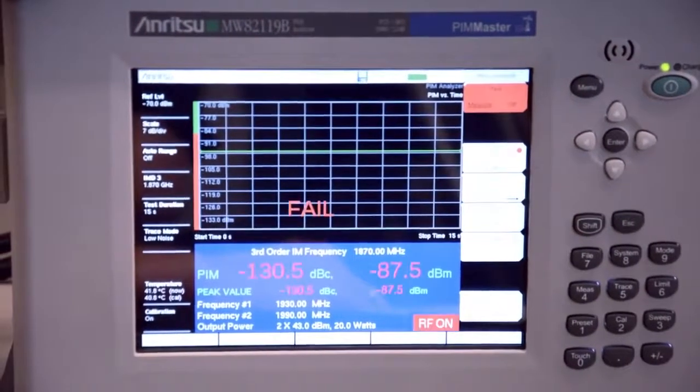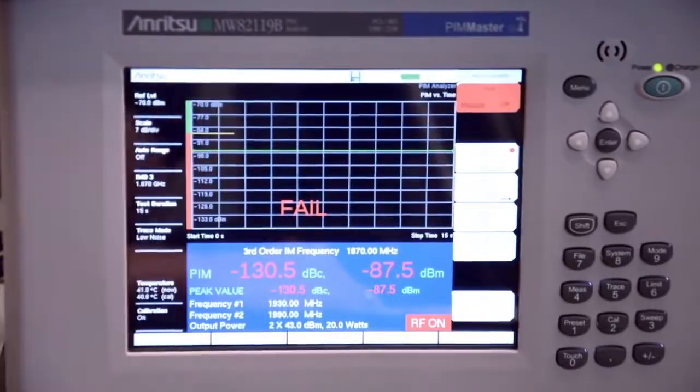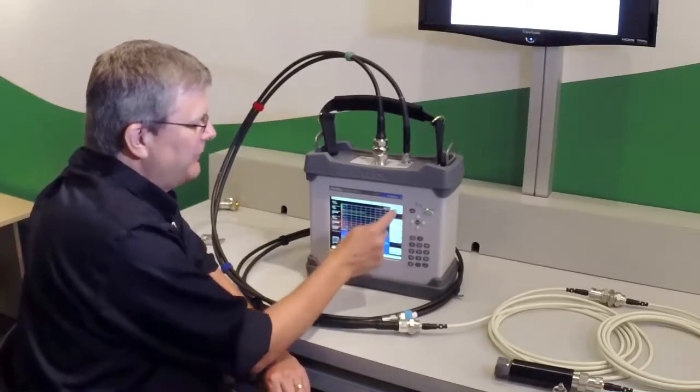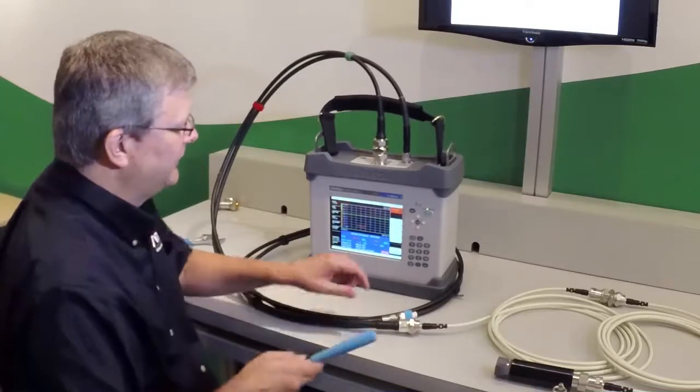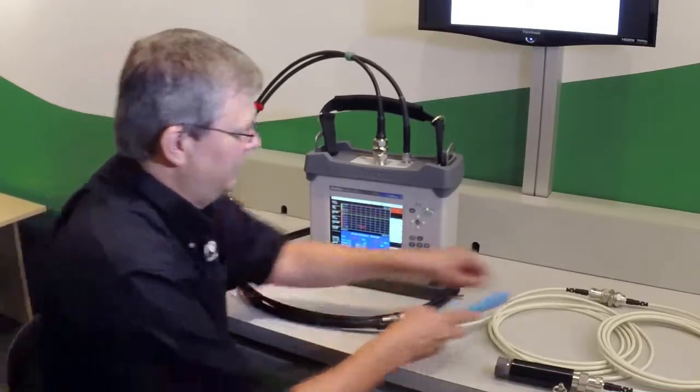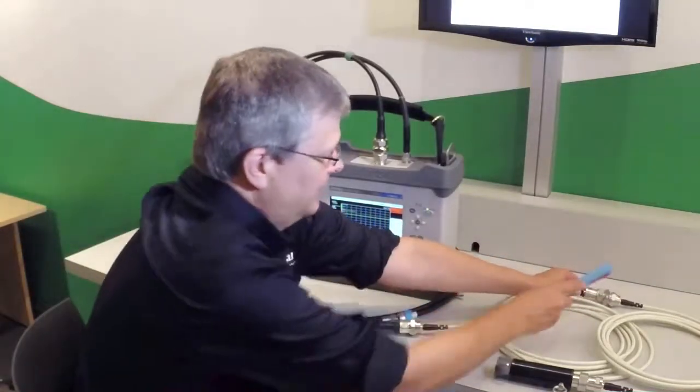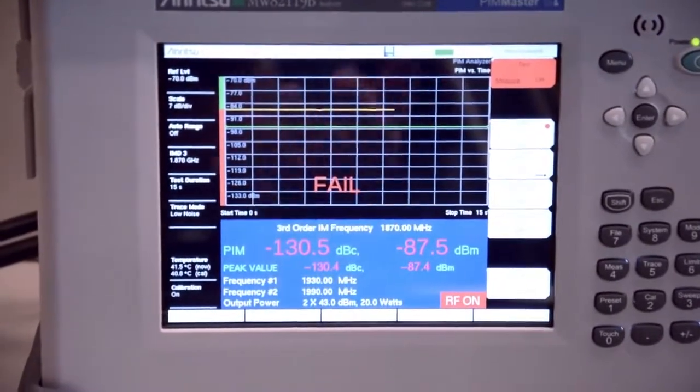We start the test, and we see that we have a failure. If I was doing this test with a traditional PIM analyzer, the first thing I would do is start tapping on the connections, trying to find the location of that PIM source. As you can see here, I don't have any indication where it is.